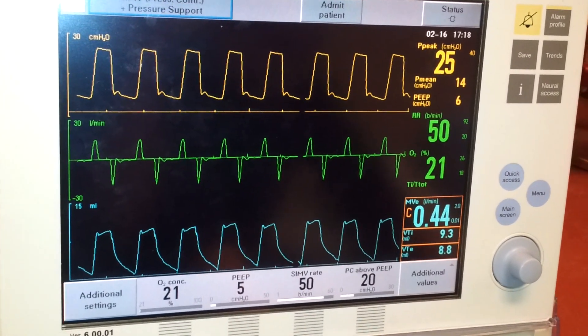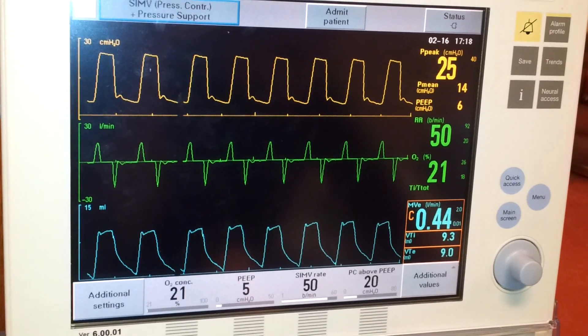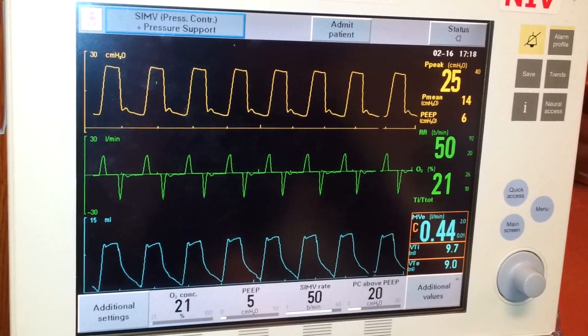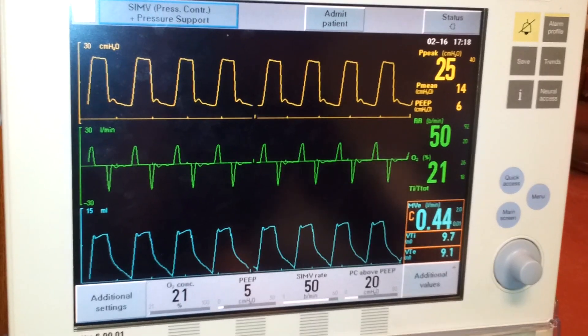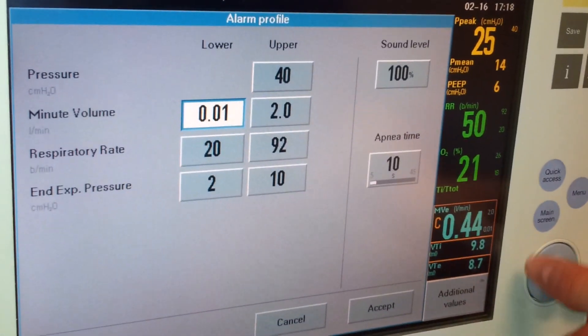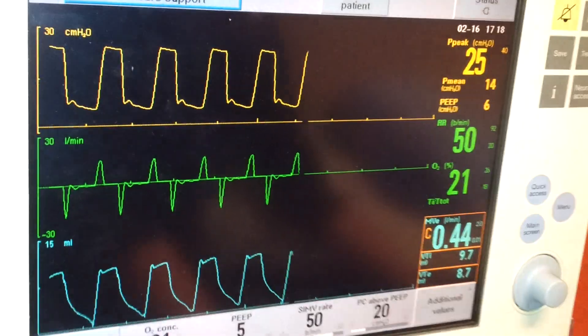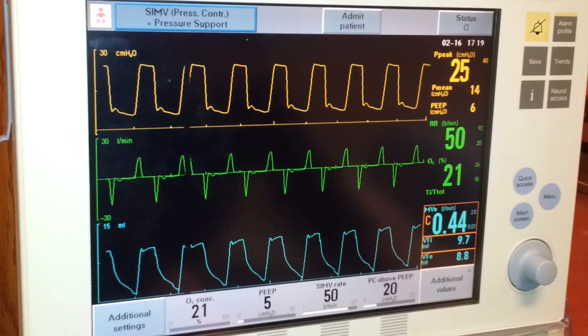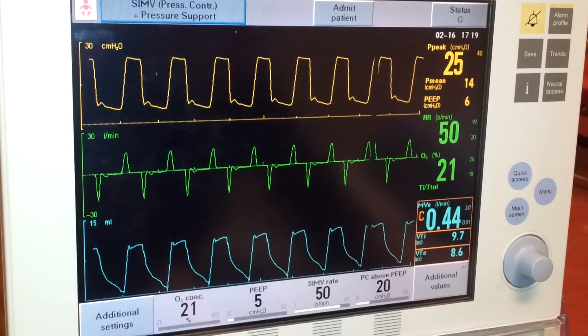The alarms can be a major issue in premature neonates being ventilated with tubing compliance turned on. The minimum minute ventilation alarm is 0.01 liters per minute. When the tidal volume being measured is essentially zero, the minute ventilation will also be zero and the ventilator will alarm. The lowest the alarm can possibly go is 0.01. So in the case of low birth weight infants, you would turn tubing compensation off to increase the tidal volume being read and to avoid unnecessary alarms.